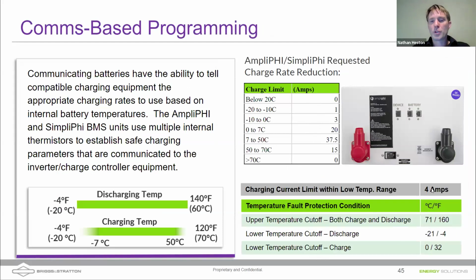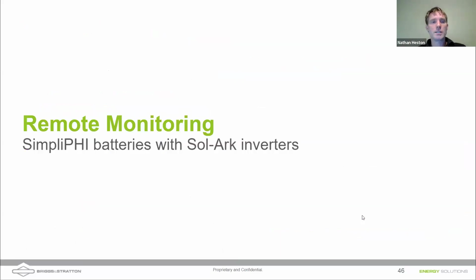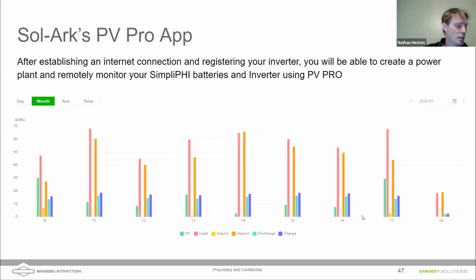There's also the fault protection given for you here. So if you have your batteries in an extreme cold situation, especially in a time of use situation in which the batteries are just sitting idle and not discharging or charging, you could get into a temperature fault, which should automatically resolve itself unless you get below negative 21 Celsius, in which case it'll require a manual reset. So I'm just about out of time.